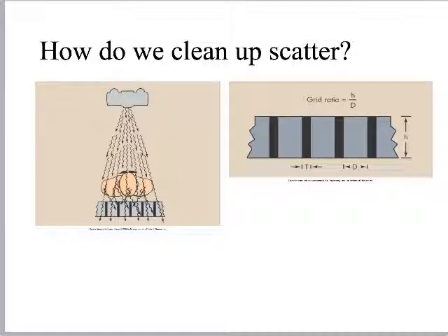For our purposes in x-ray, this is a potential because we do portable film. And anytime we're doing a portable on a patient slouched over in the bed, it's very easy to angle the grid and to cause that kind of grid cutoff, is what we call it, or a grid artifact. We can also imagine it'd be wrong if we flip this thing upside down, which is generally very difficult to do, but that can also cut things off. If we use the grid inappropriately, it can cut things off.